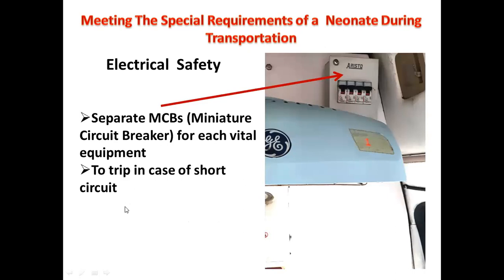In our ambulance we have an incubator, a radiant warmer, and a pump. Each major equipment has its own MCB. So if there's a problem with one, only that one will trip while the others keep running. Otherwise, if we keep just one MCB and it trips, you won't know where the fault is.